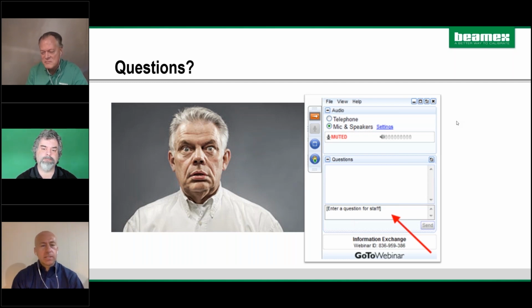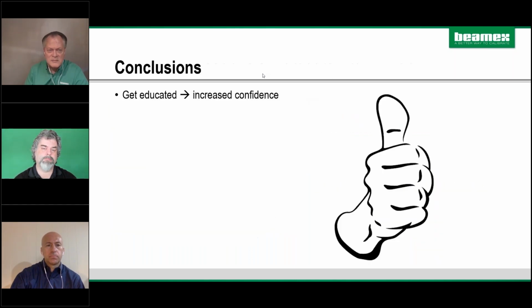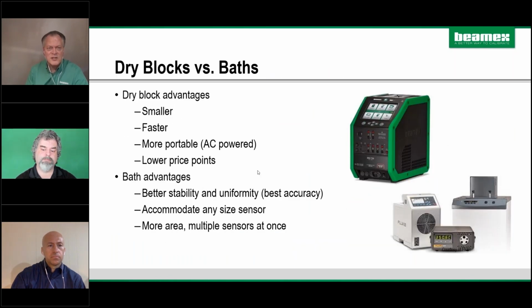So another thing that came up here is whether you could summarize the pros and cons for dry block versus temperature bath. Well, can you see my slide? I changed it. Yep. You can buy a dry block that you can literally hold in your hand. It's like holding a Bible or something, and they're not very accurate. But if you put the reference probe in there, it can work pretty well. If you're working in the shop and not having to carry the bath around, then the bath might suit you if you're looking for good accuracy.